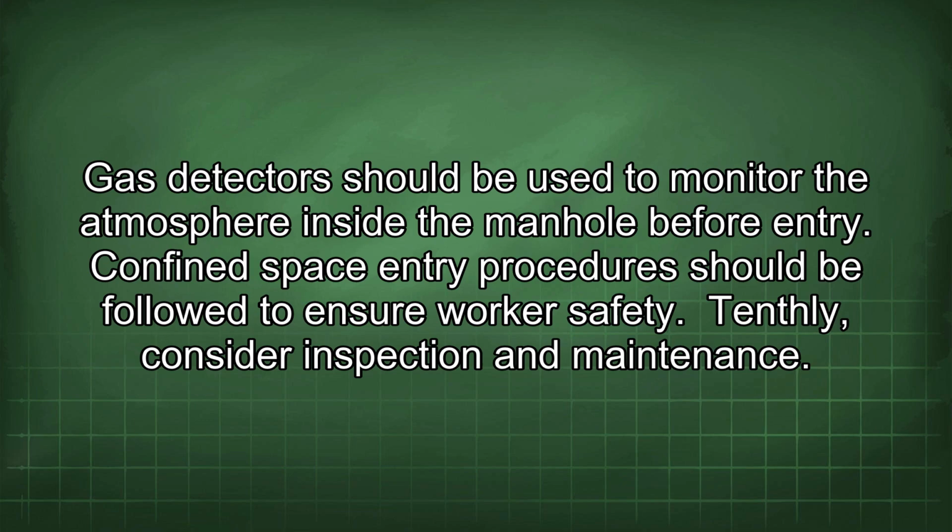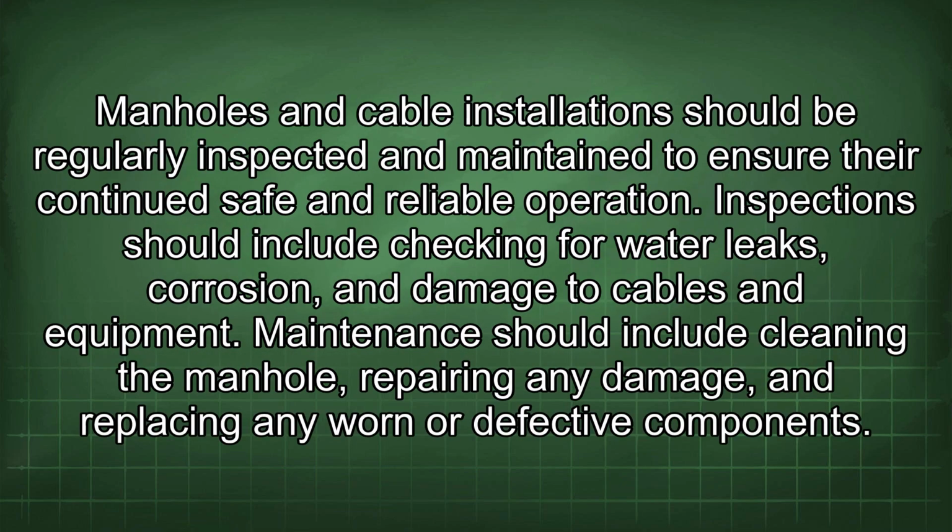Tenthly, consider inspection and maintenance. Manholes and cable installation should be regularly inspected and maintained to ensure their continued safe and reliable operation. Inspections should include checking for water leaks, corrosion, and damage to cables and equipment. Maintenance should include cleaning the manhole, repairing any damage, and replacing any worn or defective components.